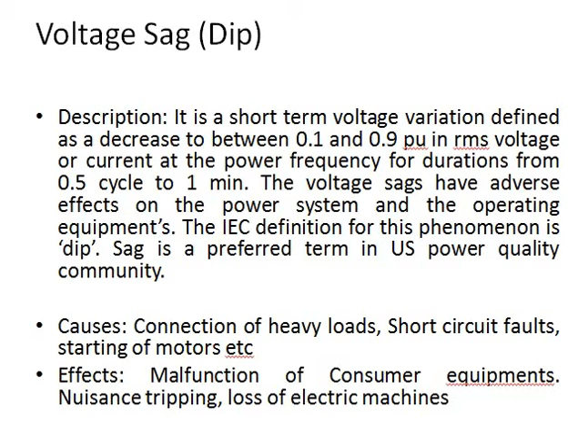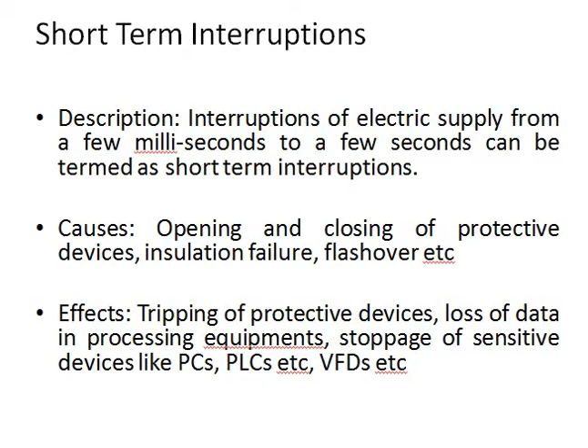Short-term interruptions. Now, interruptions of electric supply from a few milliseconds to a few seconds can be termed as short-term interruptions. Causes: opening and closing of protective devices, insulation failure, or flashover are some of the causes of short-term interruptions. The effects are tripping of protective devices, loss of data in processing equipments, stoppage of sensitive devices like PCs, PLCs, or VFDs, because it's going to have an impact on the operation of the PCs. The PCs may shut down abnormally. For the variable frequency drive, you may have an adverse effect of short term interruptions as well.